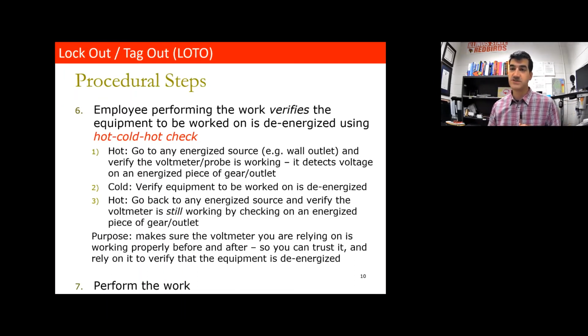Step two is you do your cold check. That's where you go to the piece of equipment you're actually going to work on, and you measure the voltage inside that cabinet, or on the equipment, whatever it is you're working on, and it should be de-energized. If it's not, you stop and back up, go back to step one and redo this. Step two is taking the multimeter, measuring the equipment. It should be de-energized. That's the cold part of the hot, cold, hot check.